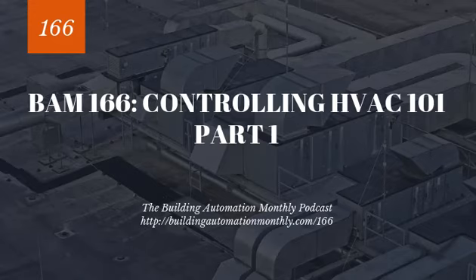So how do we control temperature in spaces? Well, typically we will introduce more cold air. We'll have a min and max, especially on a VAV system, or we will have a discharge air reset on a CAV system. So we introduce more cold air, either by decreasing the temperature or increasing the airflow. In the case of heating, we decrease the airflow, or we increase the temperature, or we have reheat at VAVs.